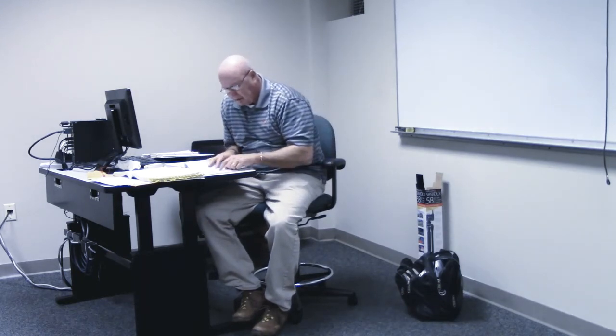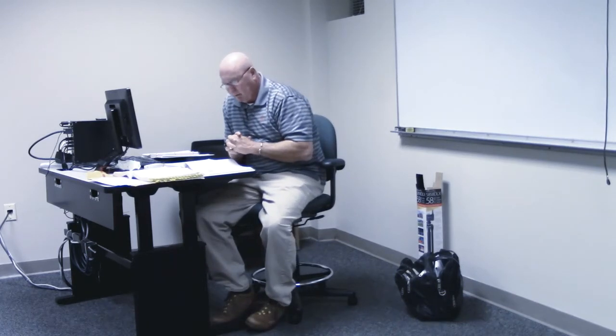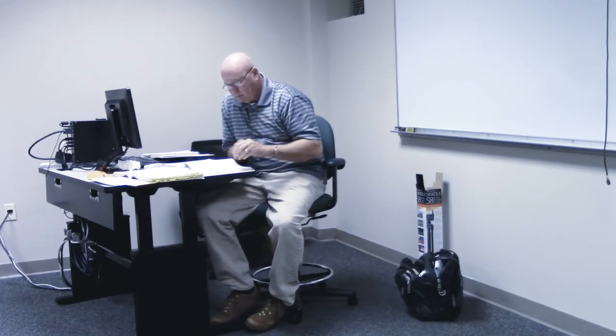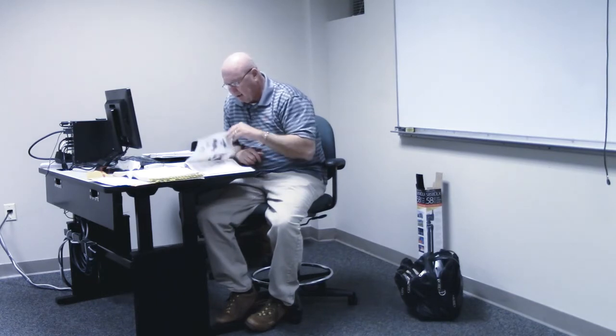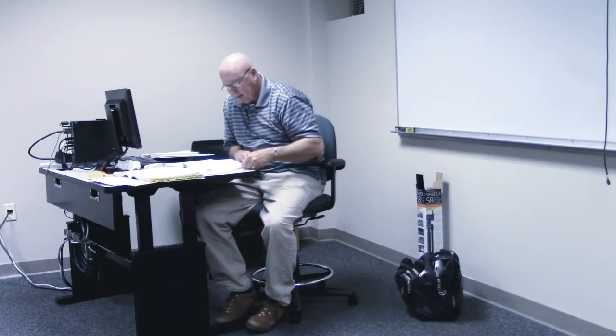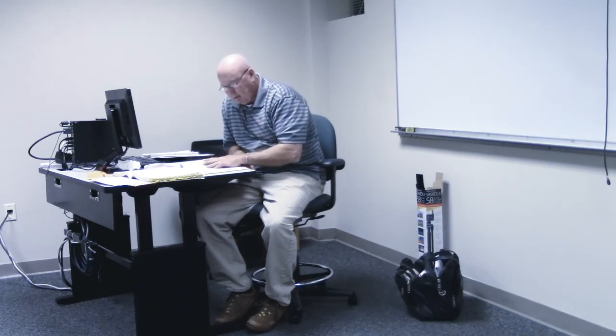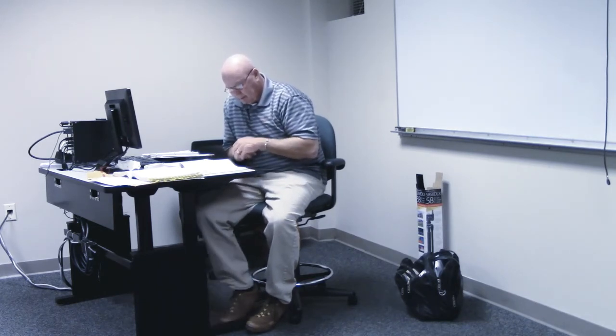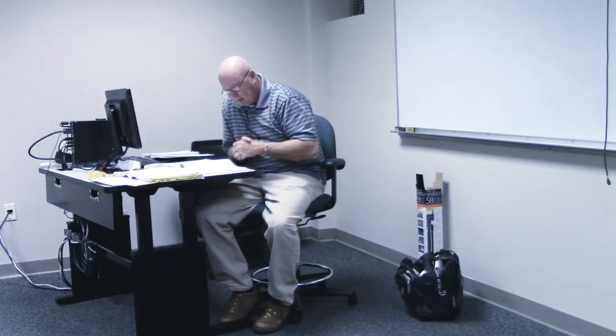If you look, it says figure 11, so let's turn over. Figure 11, isolated power panel, you see an example of one there. Not your normal power panel, is it? A lot more money. But it is required in this case, an isolation power panel, so it's not going to be your typical power installation. We see here the installation for that is shown on page 24.